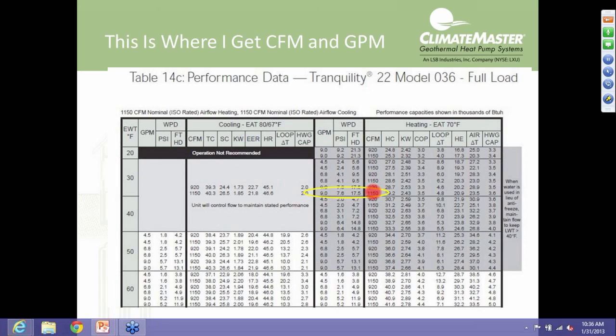The formula for heat of extraction, heat of rejection, which I'm going to show you here in a moment, is delta T times gallons per minute times a fluid factor. Well, we've got our gallons per minute now dialed into 9 gallons per minute. We're going to get our delta T right off the screen, because we look right there on the control diagnostics at our entering water and our leaving water, subtract the 2, and that's our delta T. The fluid factor is going to be one of 2 numbers, either 500 for water or 485 if it's an antifreeze solution. Multiply those 3 numbers, and we're going to get a calculated heat of extraction.